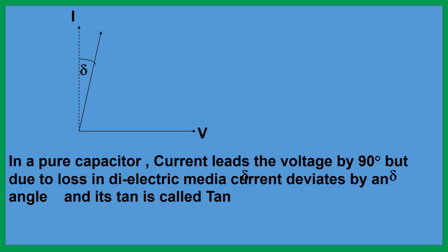In the next slide, I have shown what tan delta is. You can see the picture here. For a pure capacitor, current leads voltage by 90 degrees, but due to loss, it is called the loss angle. It deviates from its 90 degree position towards the voltage line. So this angle is delta and its tan is called tan delta, and I have told you it should be 0.007 or less. Okay.